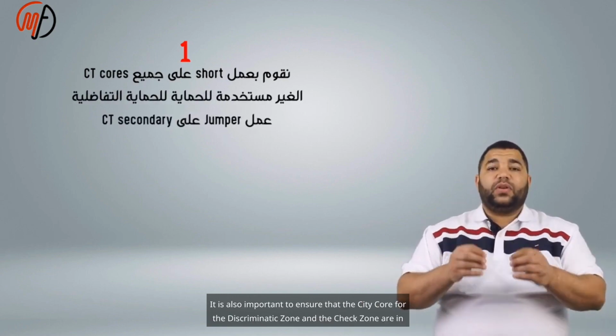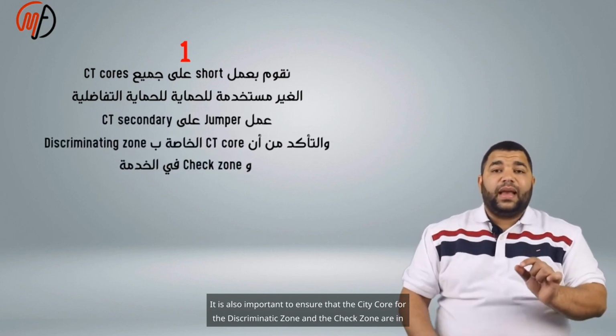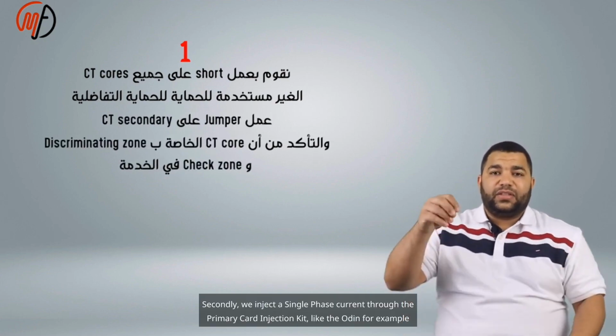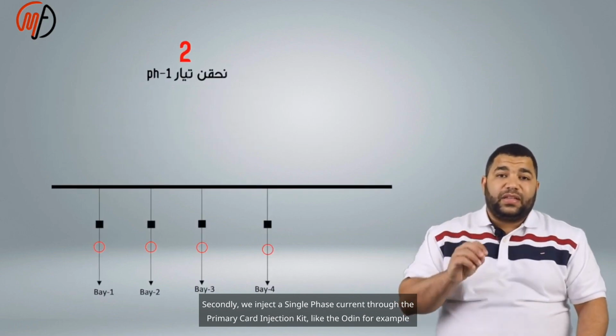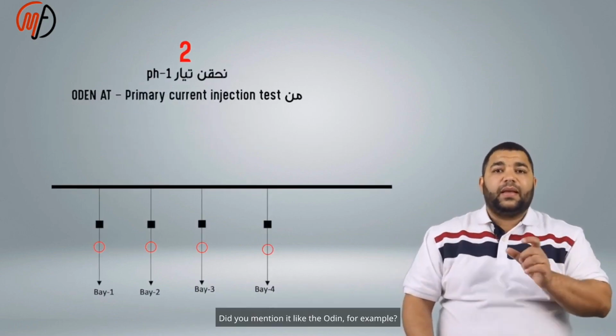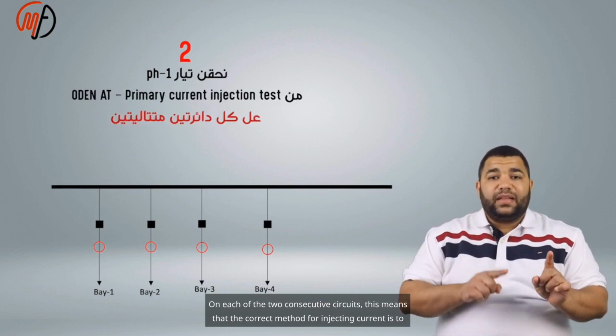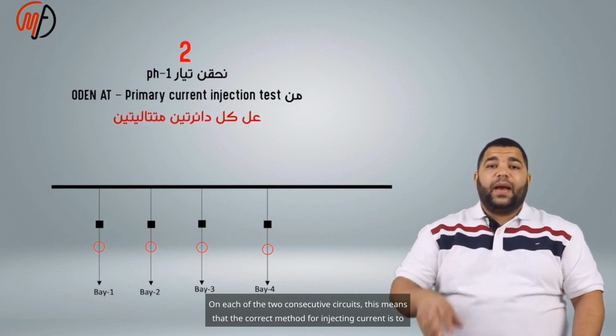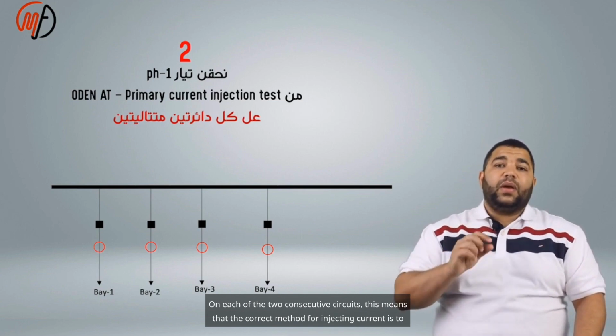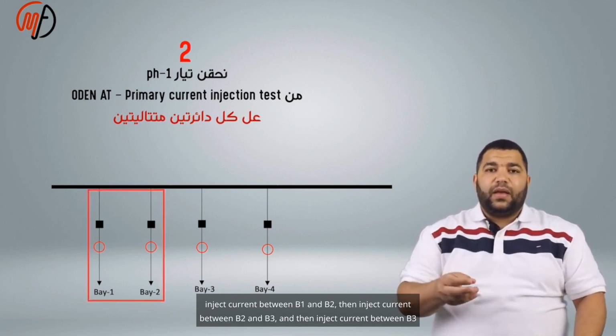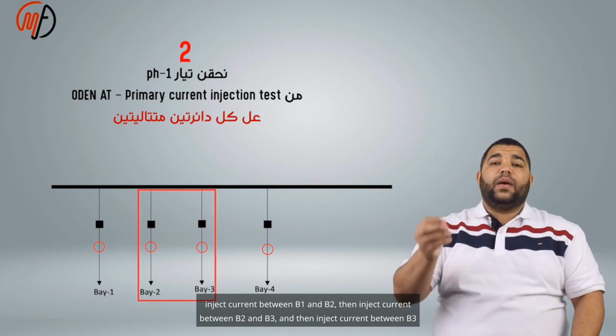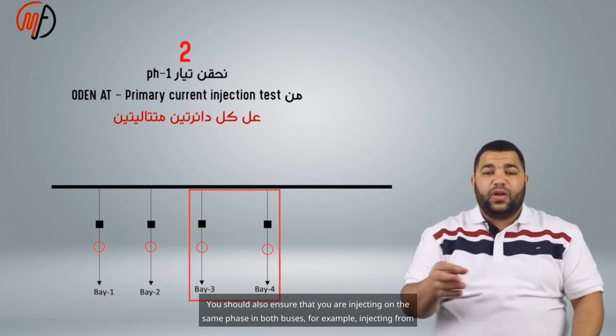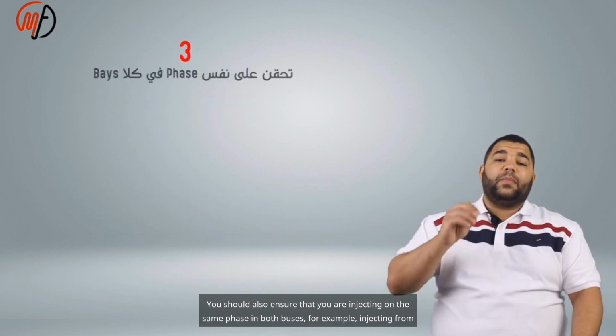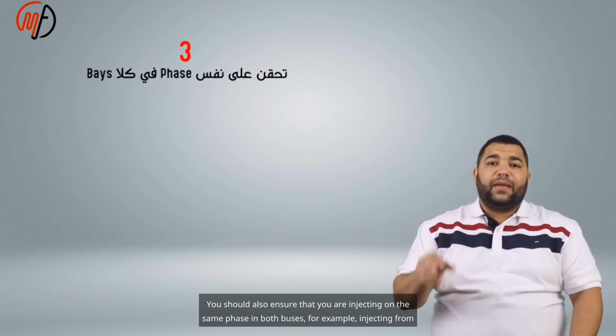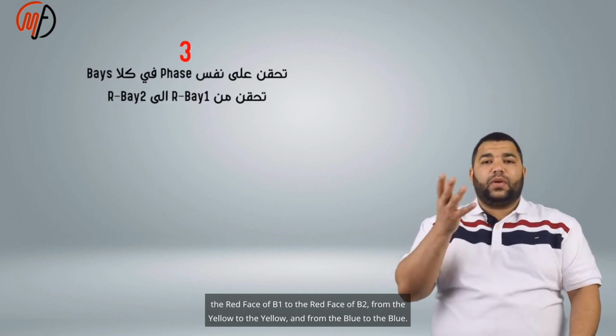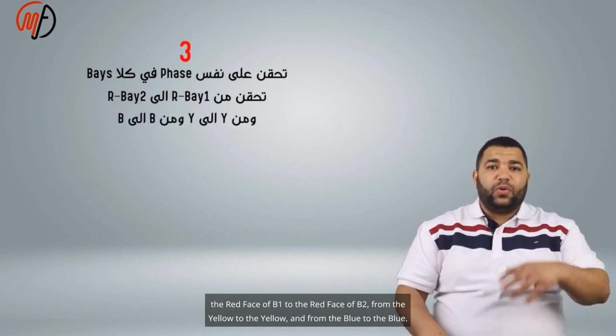It is also important to ensure that the CT core for the differential zone and the check zone are in service. Secondly, we inject a single-phase current through the primary current injection kit, like the Omicron, for example, on each of the two consecutive circuits. This means that the correct method for injecting current is to inject current between B1 and B2, then between B2 and B3, and then between B3 and B4, and so on. You should also ensure that you are injecting on the same phase in both buses, for example, from the red phase of B1 to the red phase of B2, from the yellow to the yellow, and from the blue to the blue.